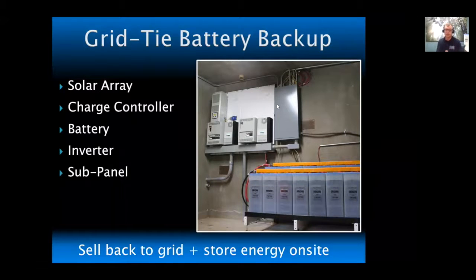Other items you see here, the inverter. The inverter is able to interface with the grid and with a generator, sometimes both at once, so that the system can, at the last moment, if the battery gets low, draw from the grid and keep the system up and running, or call on a generator.